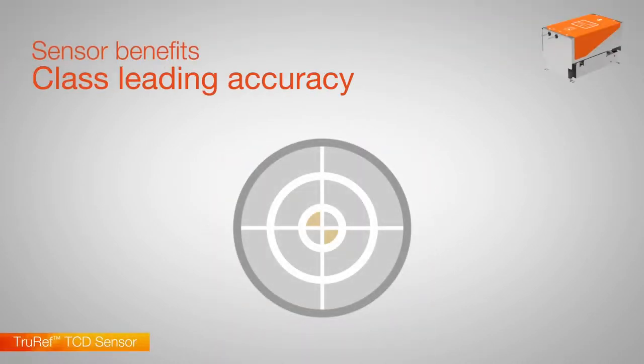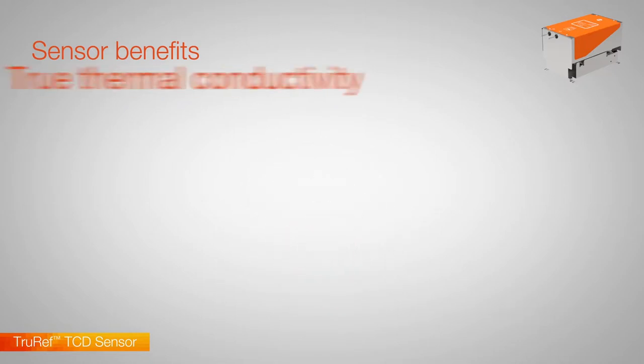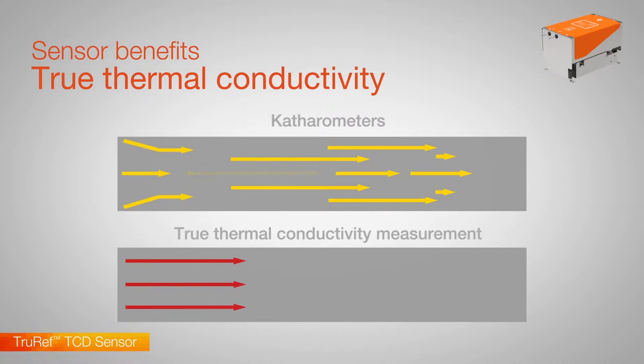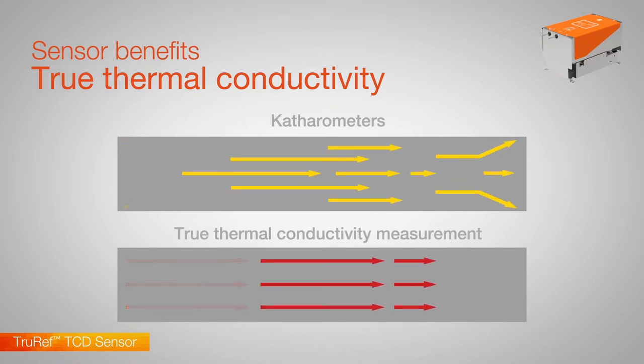With class-leading accuracy, it incorporates Hummingbird's TruRef technology, a unique thermal conductivity measurement. Unlike catharometers, the effects of sample pressure and flow rate are effectively eliminated.